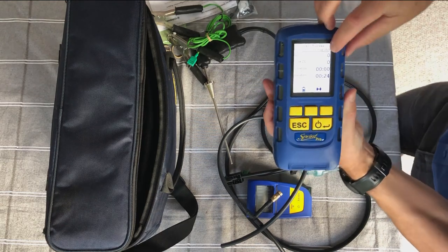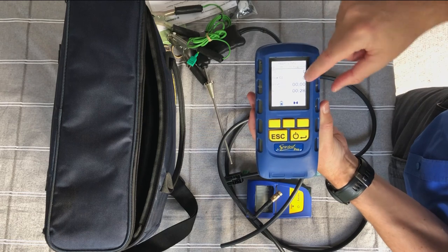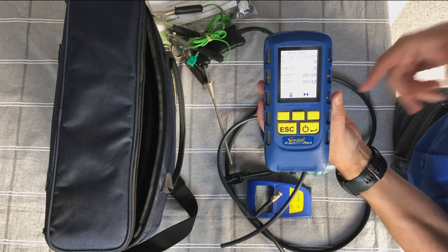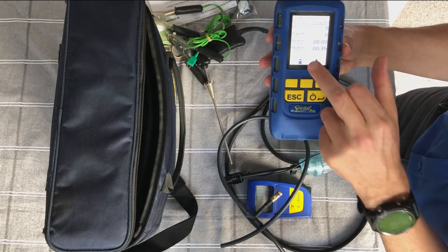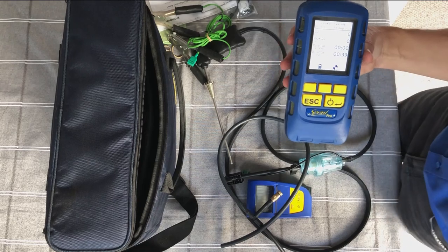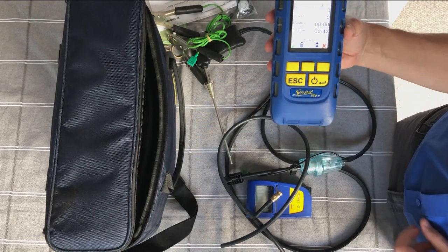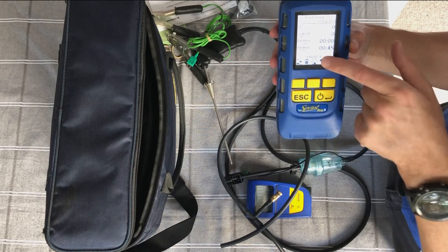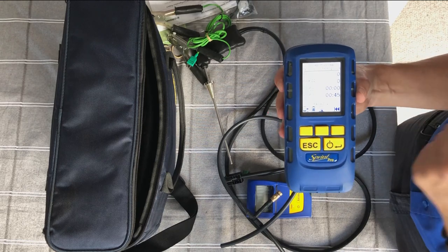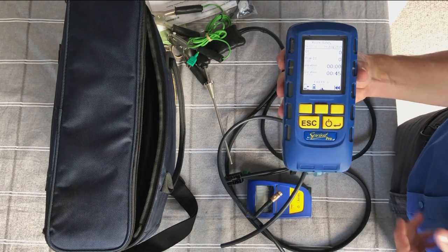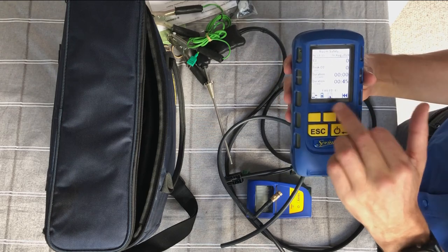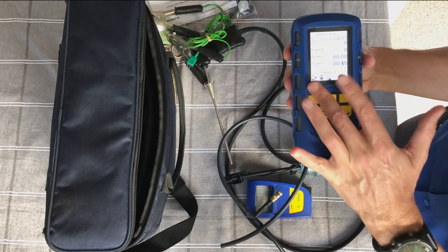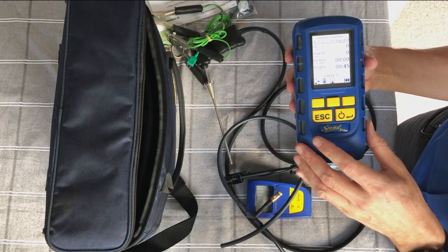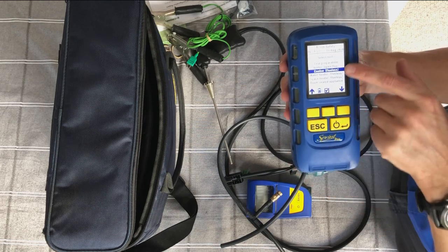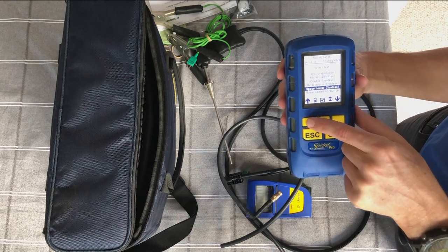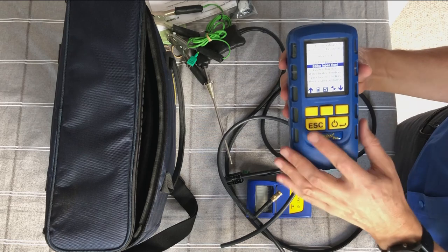So if it was at 15, and it's now at 8, you can see it's coming back down again. All that information helps you when you're deciding if it's a pass or fail at the end of the test. As I say, it won't let you stop the test until it's completed. The only thing I can do is press escape and quit the test, but it automatically makes it a failed test because I haven't completed the test to the British standard, which in this case is a minimum of 20 minutes, a maximum of 30 minutes. But if it reaches 20 minutes, you can then stop it, save it, pass it, fail it, whatever you choose to do, again with the green and red pass and fail buttons. But again, that would be different for the different space heaters, room heaters, boilers. The test parameters are already in there, which is really, really helpful.